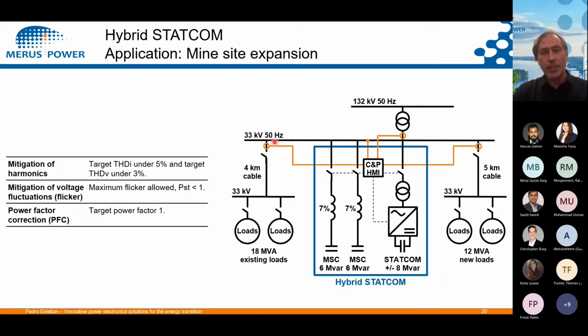We will be connecting this device somewhere in the medium voltage of the installation, typically in the substation of the mine. In this case, we can use a STATCOM to provide the dynamic output in real time, plus a couple of capacitor banks working together with the STATCOM, so we can provide extra capacitive reactive power cheaply. Again, here are some typical values required for these applications. Target power factor, of course, 1 is good to reduce the energy cost of the operations in the mine.